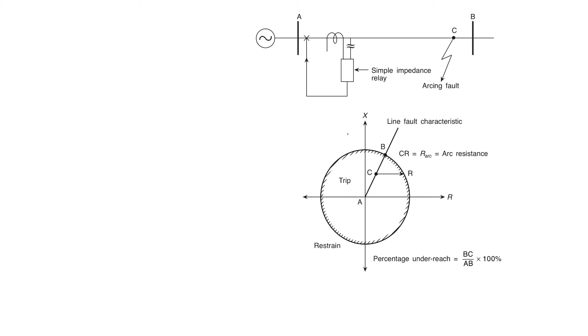So you can say that the simple impedance relay underreaches because of the arcing fault, and the percentage underreach is defined as the ratio of the distance by which the relay underreaches to the reach setting of the relay. It is given by BC, the distance by which the relay underreaches, divided by the reach setting of the relay, which in this case is AB, into 100. This is known as the percentage underreach of the relay. So from this we see that because of the arcing resistance, this relay is definitely going to underreach.